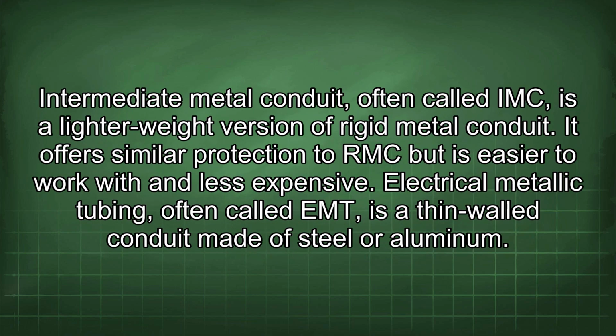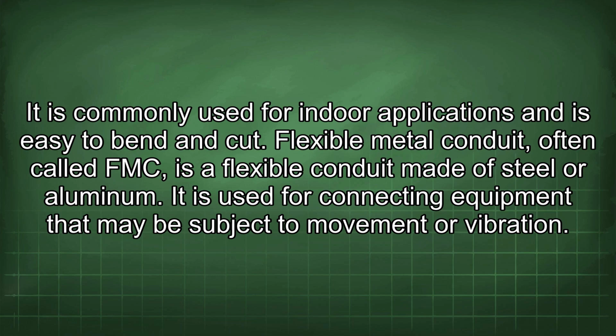Intermediate metal conduit, often called IMC, is a lighter weight version of rigid metal conduit. It offers similar protection to RMC but is easier to work with and less expensive. Electrical metallic tubing, often called EMT, is a thin-walled conduit made of steel or aluminum. It is commonly used for indoor applications and is easy to bend and cut.